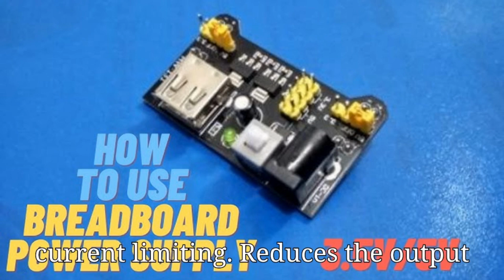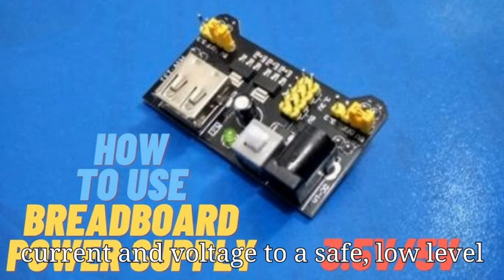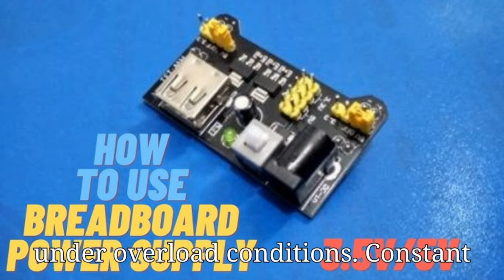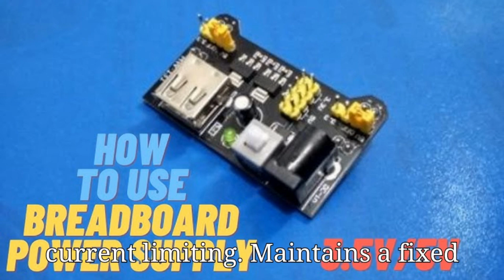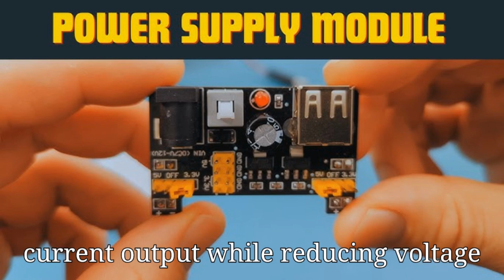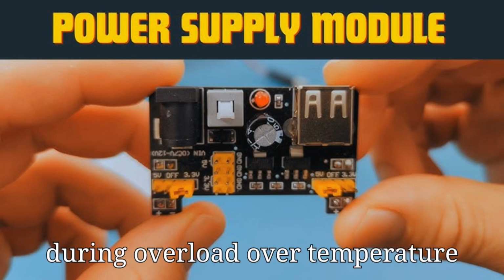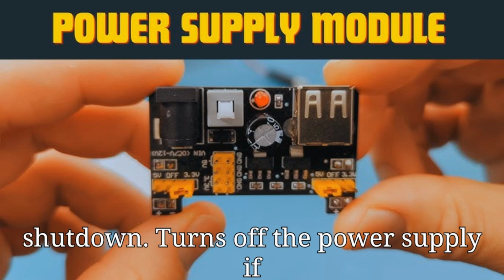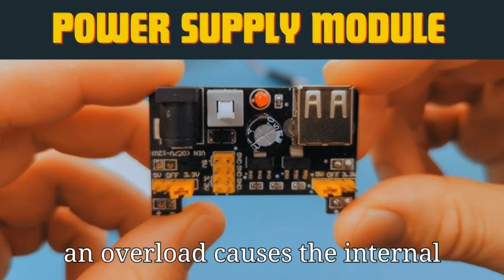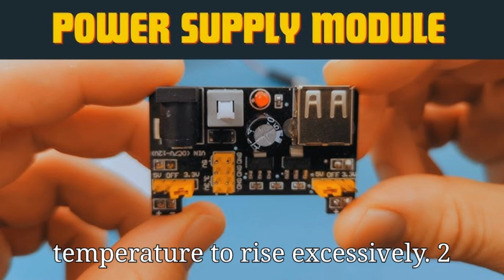Foldback current limiting. Reduces the output current and voltage to a safe, low level under overload conditions. Constant current limiting. Maintains a fixed current output while reducing voltage during overload. Overtemperature shutdown. Turns off the power supply if an overload causes the internal temperature to rise excessively.